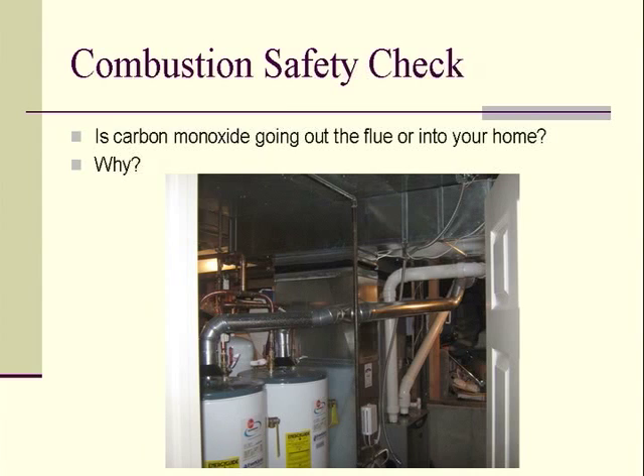Water heaters — this is a good example of a water heater that has a lot of potential to leak carbon monoxide into your home when it's in operation. The issue here is the flue is practically horizontal and runs for a long length. Water heaters, in order to exhaust carbon monoxide from your home, work a lot like a fireplace, where that flue has to get hot to get the carbon monoxide out. The fact that the flue has heated up is a lot of the reason it can get that carbon monoxide out.